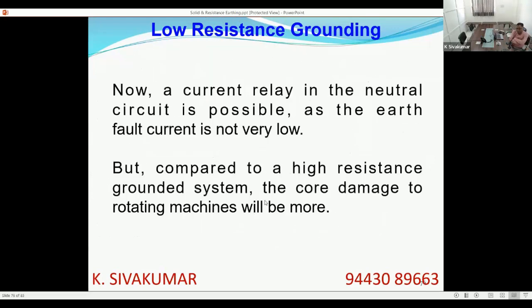Now, since the current is 400 ampere, or more than 100 ampere, you can always provide a current transformer in the neutral to ground path and provide a relay. It can be an IDMT relay or an instantaneous relay depending upon your coordination requirement. You can select an appropriate relay and connect across the NCT. But here, since you are allowing a higher current, the probability of core damage is much higher.